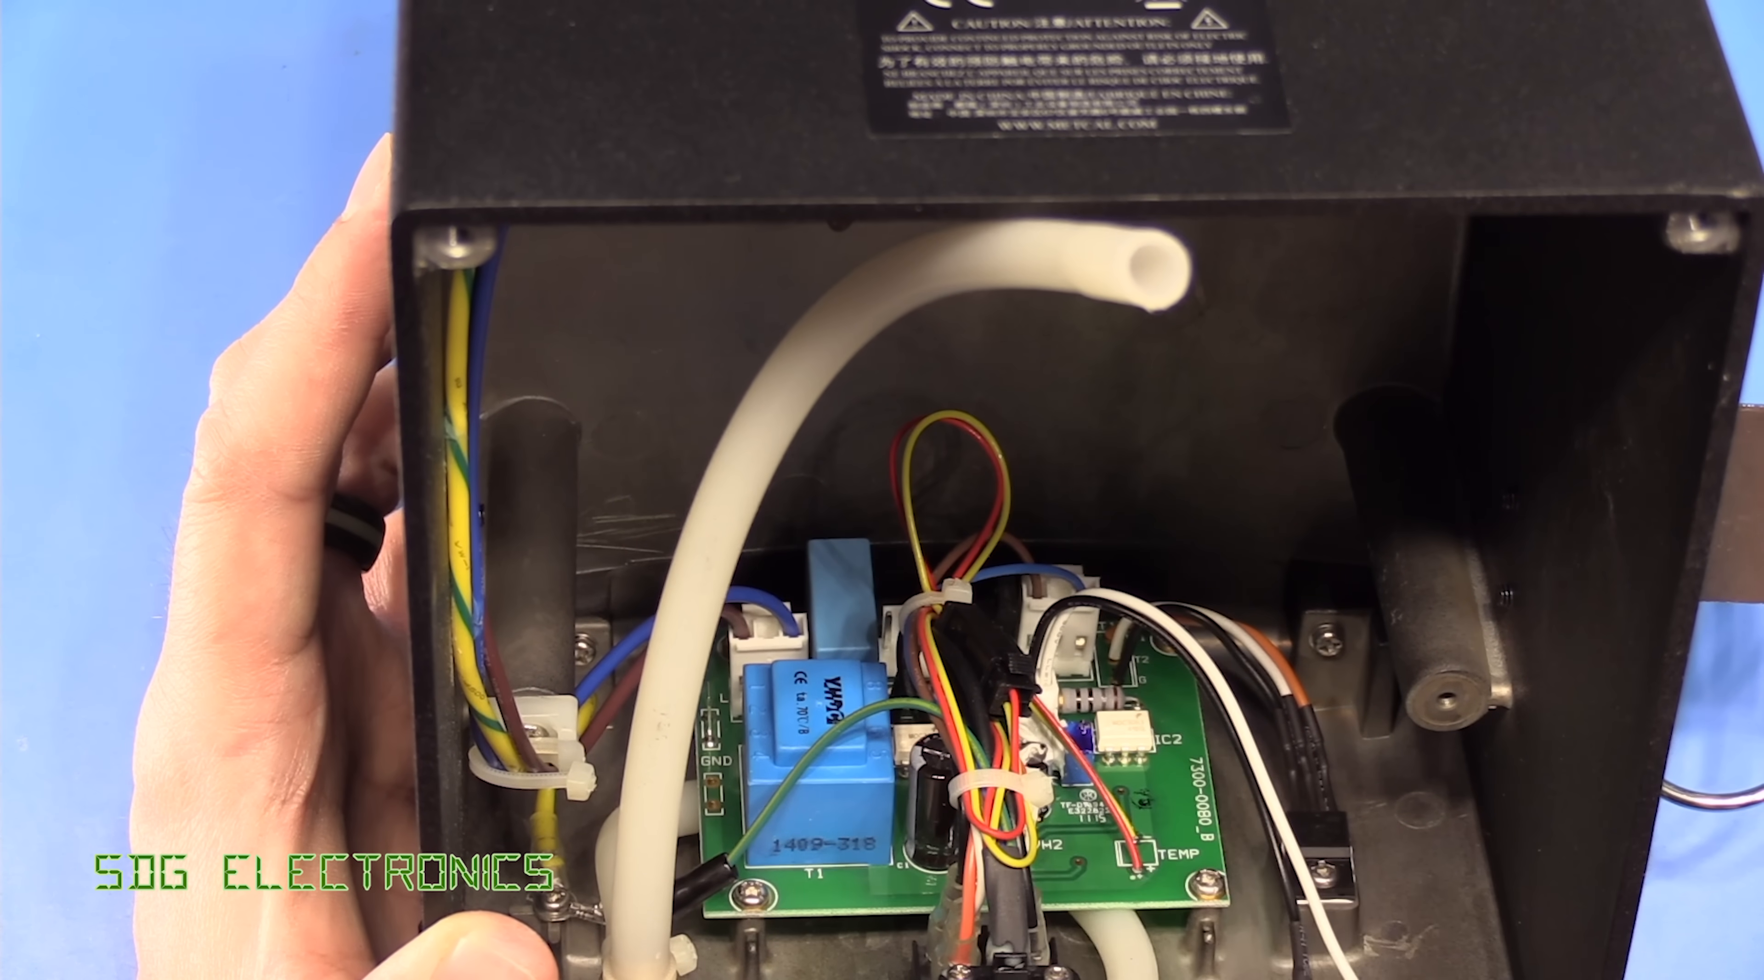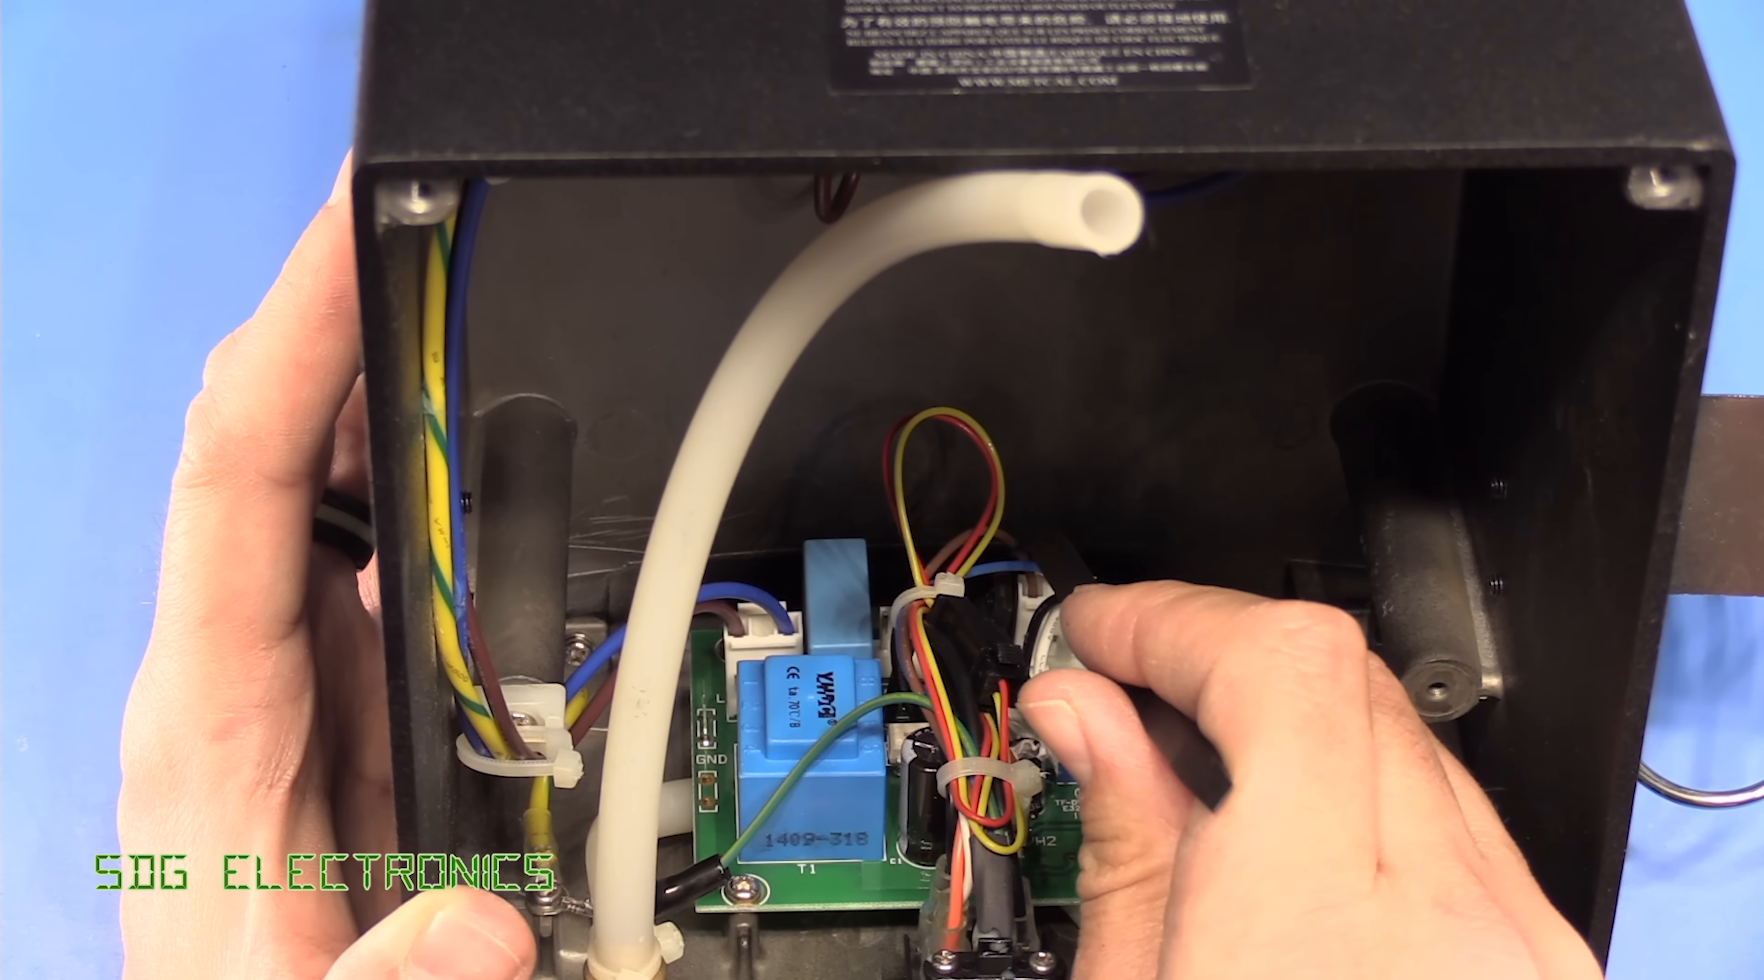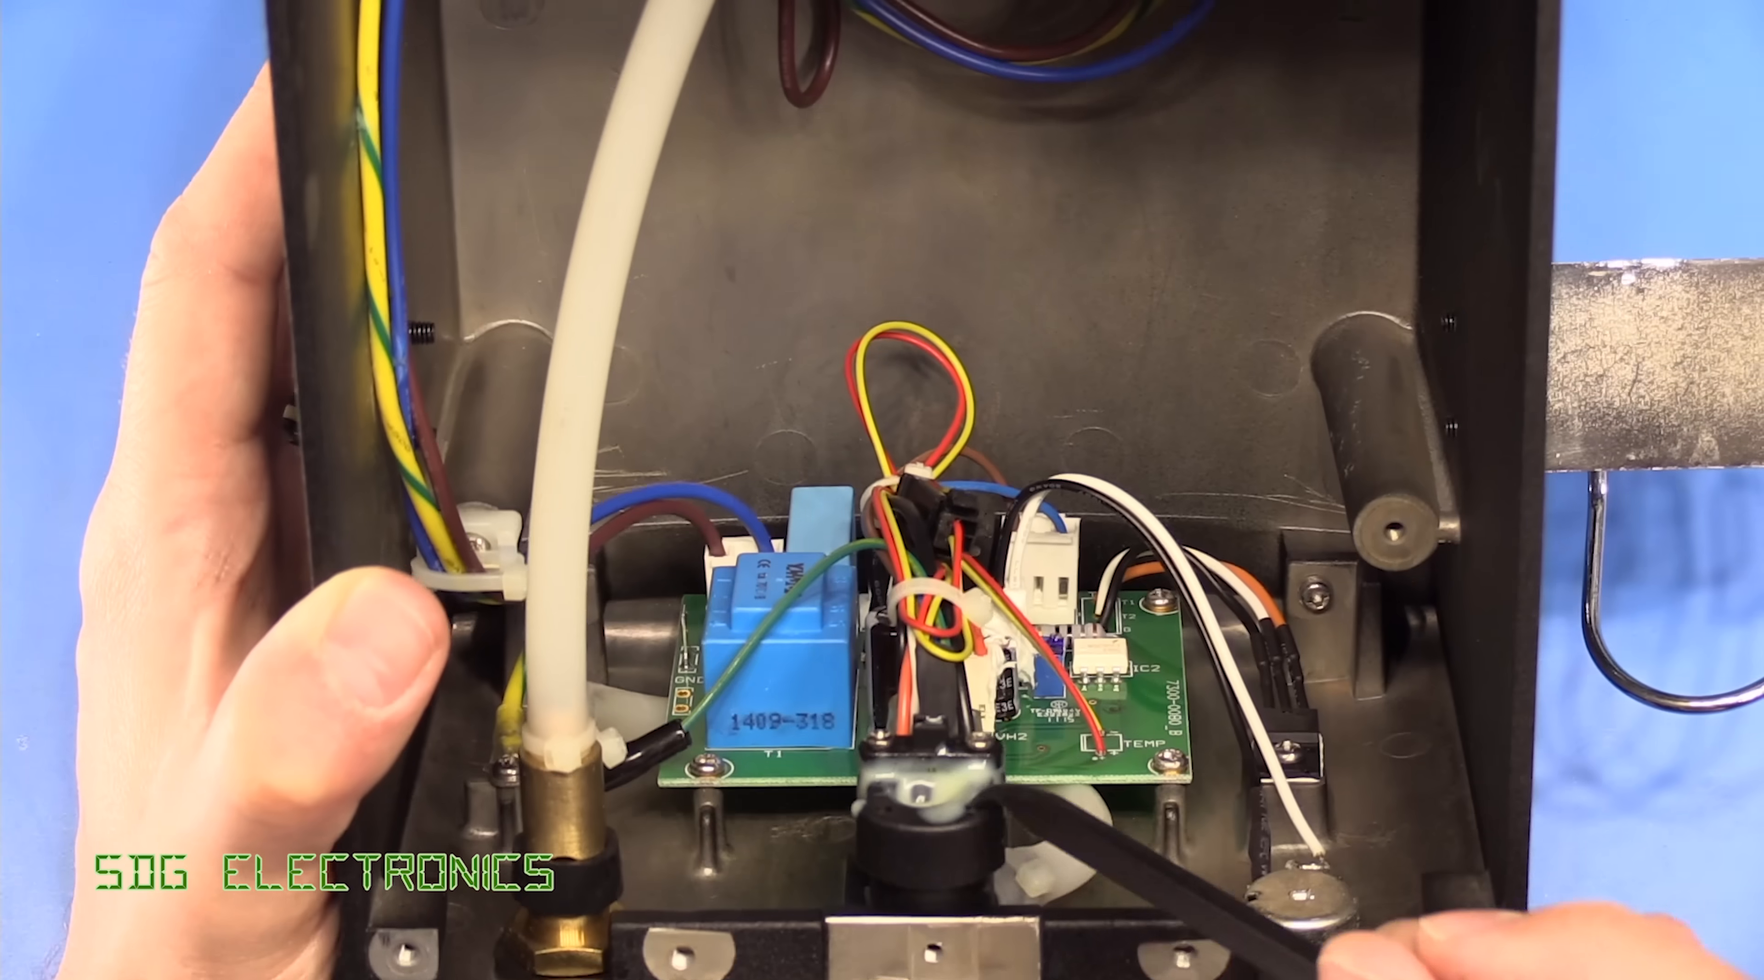And then on the PCB itself we've got the AC coming in, we've got a filter, big capacitor here as well for a bit of power factor correction. We've got a little transformer, we've got one connector at the back there that goes off to the pump, and then we've got a connector just here with those brown and blue wires that go off to the heater through the tubing. And then it looks like our temperature sensor is just on the yellow and red wire that also go through that tubing to the handpiece.